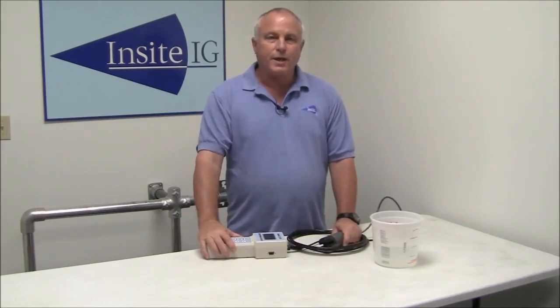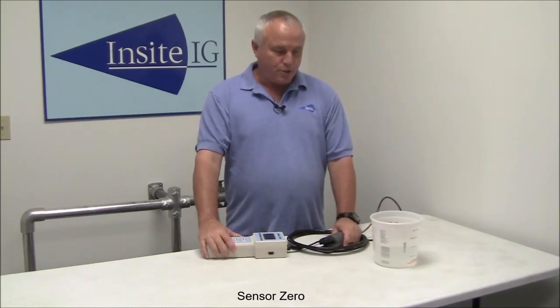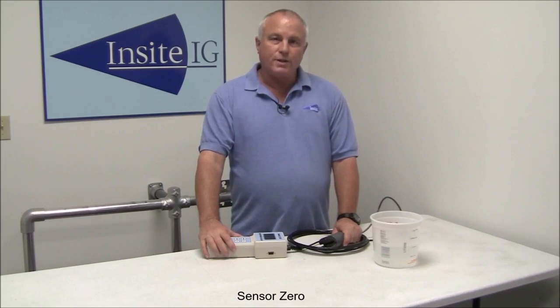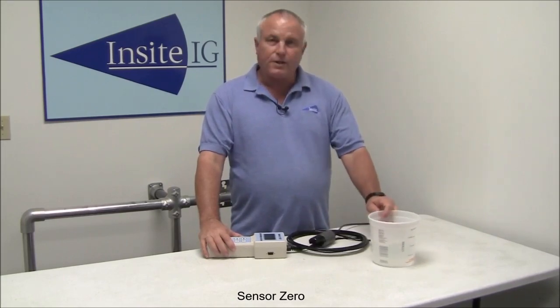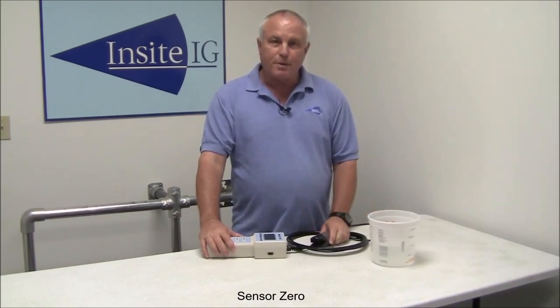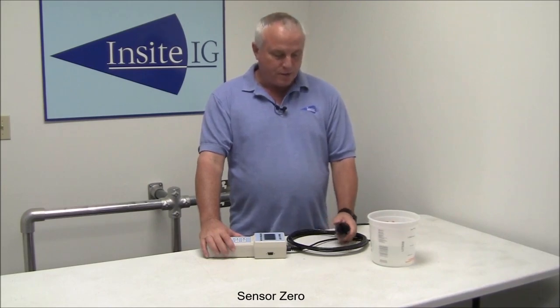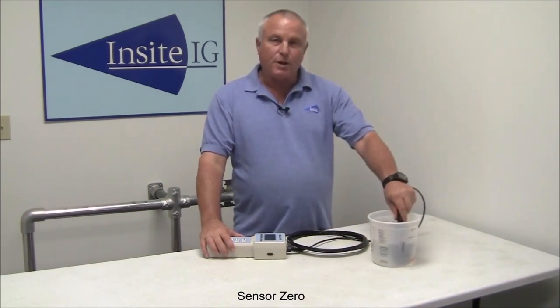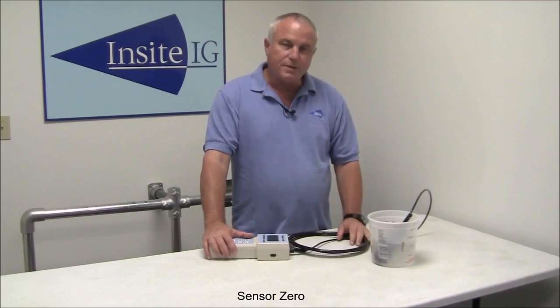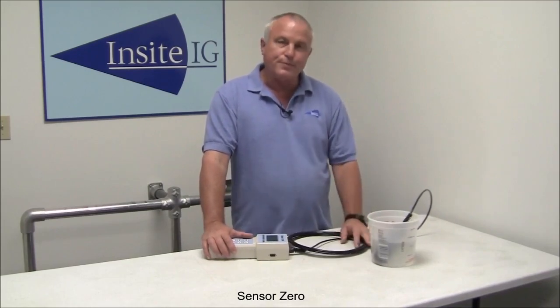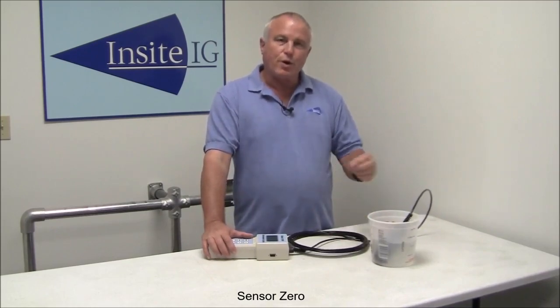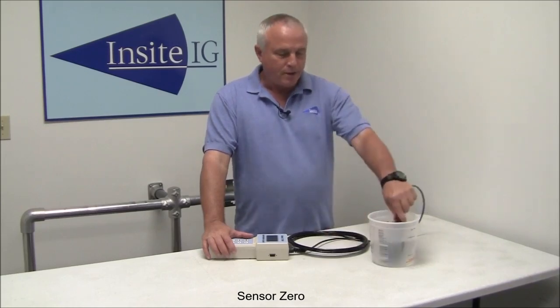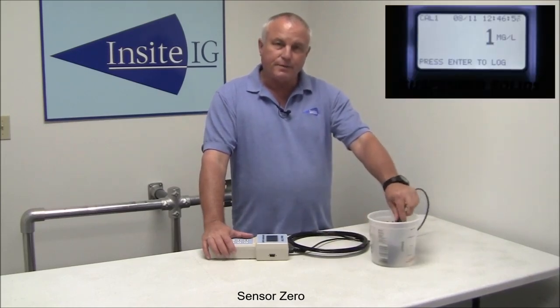The first step to do the calibration is to do the sensor zero. All you need to do this is a container of clean water. You can do it in the lab at the bench. You don't have to be out in the field to do this. You just simply put the sensor in the clean water, let it sit for a couple of seconds to stabilize the temperature. And what you're trying to do is make sure no air bubbles form on it. And then just kind of gently swish it around a little bit.